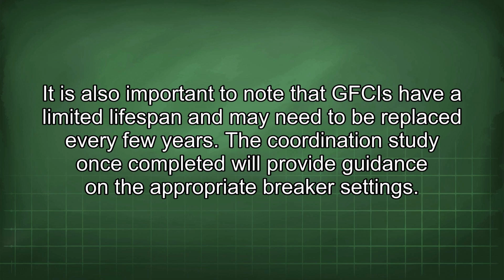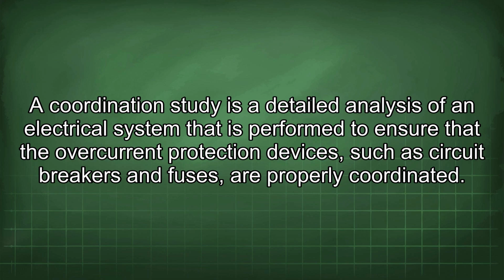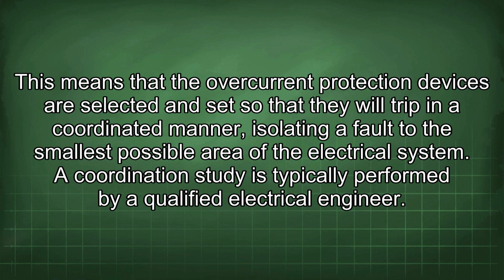The coordination study, once completed, will provide guidance on the appropriate breaker settings. A coordination study is a detailed analysis of an electrical system that is performed to ensure that the overcurrent protection devices, such as circuit breakers and fuses, are properly coordinated. This means that the overcurrent protection devices are selected and set so that they will trip in a coordinated manner, isolating a fault to the smallest possible area of the electrical system.